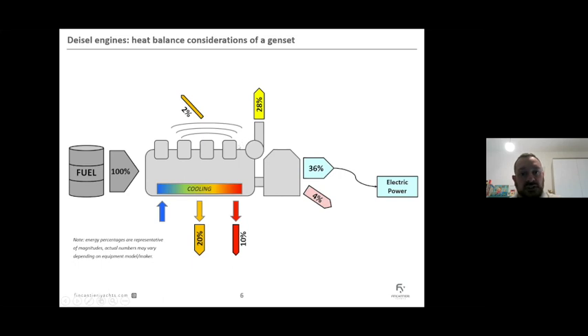What's worth noting is that both the exhaust gases and the high temperature cooling loop carry very high quality heat, available at high temperature. So simply putting this heat into seawater or air wastes potential energy that could be recovered through heat exchangers or exhaust heat boilers.